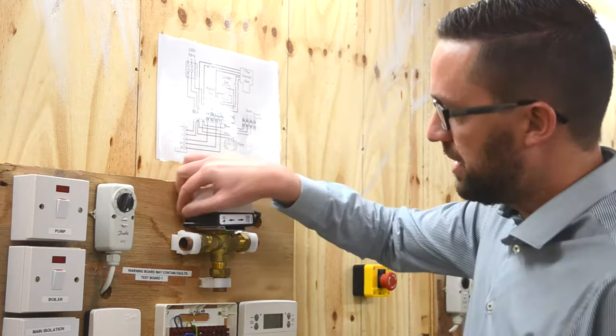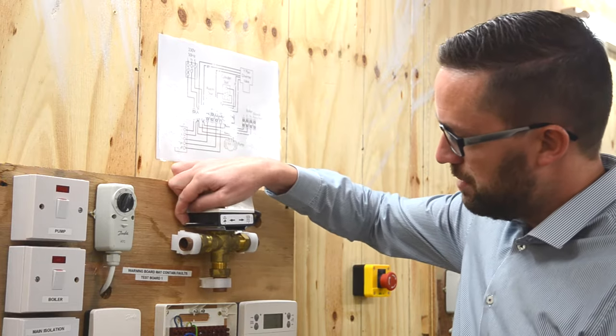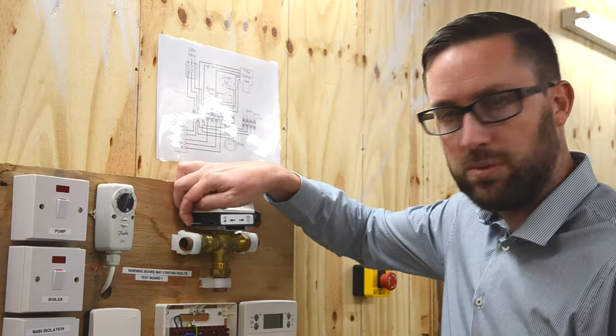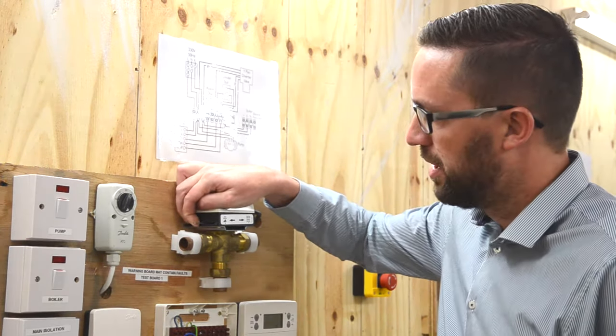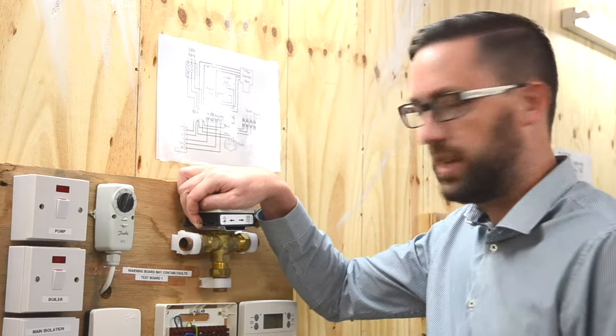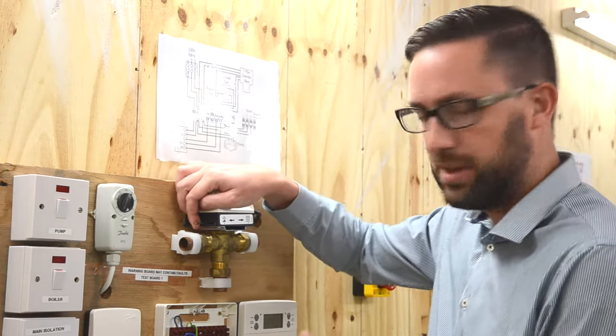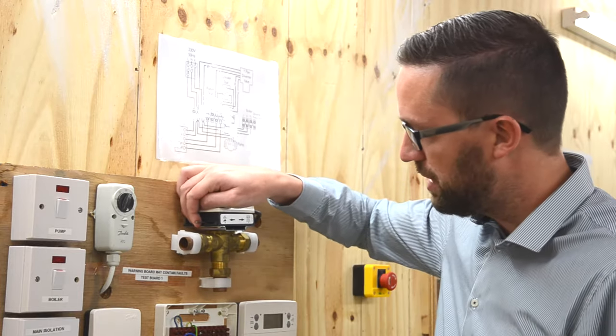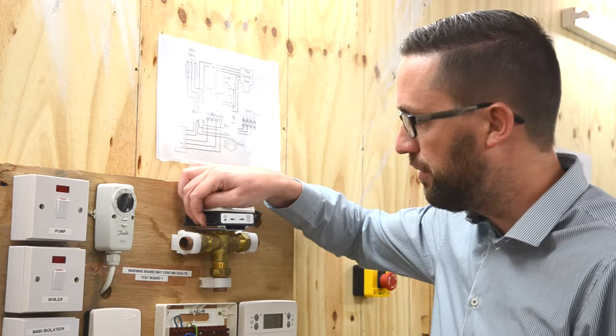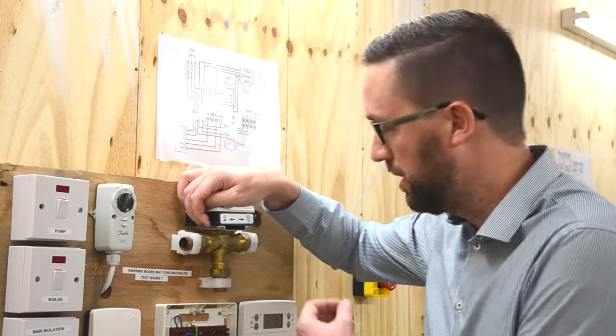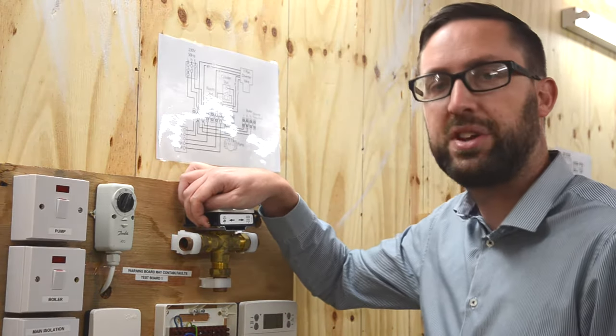So what we can do is a quick fix. As the motor opens to the heating, this lever will start to move over. When it hits a certain point, the motor is not powerful enough to get it open fully. So what we can do is give it a bit of help - we can just use our finger to gently pull the lever forward until we hear it click. That will hopefully bring your heating on.